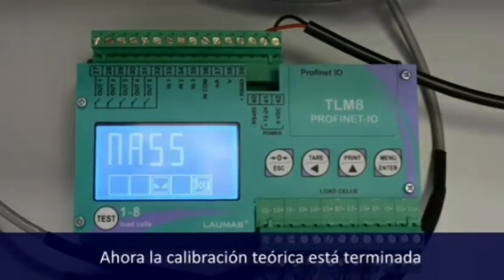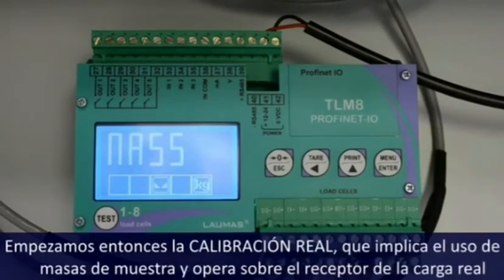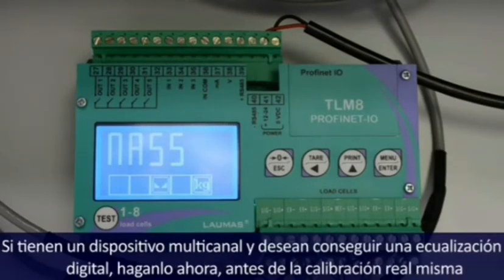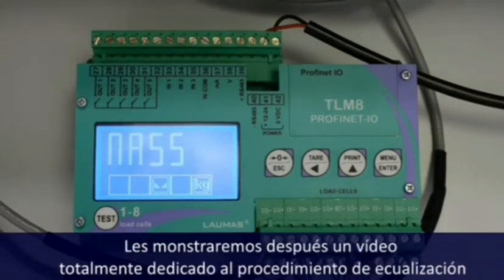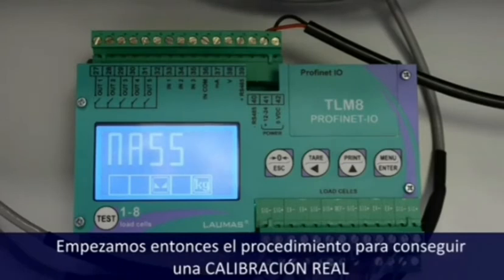Okay, now the theoretical calibration is over, and we start what we call the real calibration, that involves having sample masses and operate on the real load receptor. If you have a multi-channel device and you want to do a digital equalization, this is the moment to do it, before the real calibration. There is a dedicated video about equalization. Let's start the real calibration.